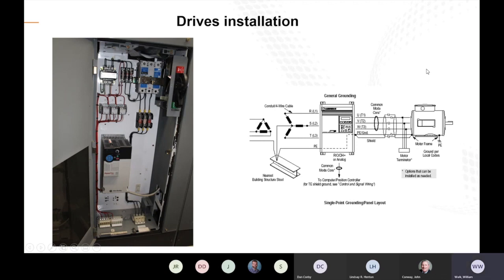Another thing to note too, whenever installing your VFD, the VFD has 2 grounds inside of it, one for your incoming line, and that's going to be on the left side of the VFD, and the one on the right side of your VFD is for the grounding termination on your motor. Whenever you're grounding your motor to your VFD, you want to use that instead of, say, installing it on any other type of ground that you might have in the system. Install it on the ground side of the VFD on the right.